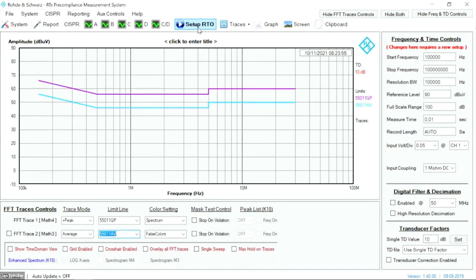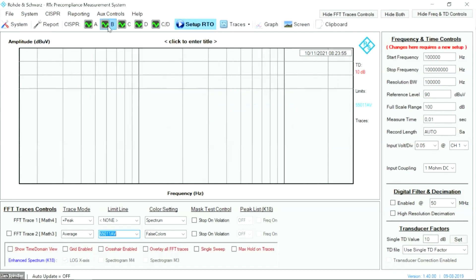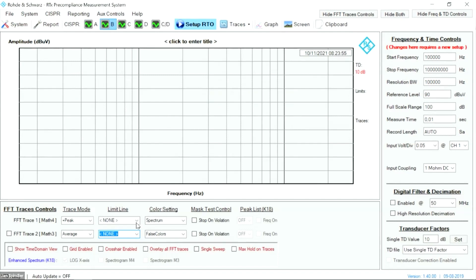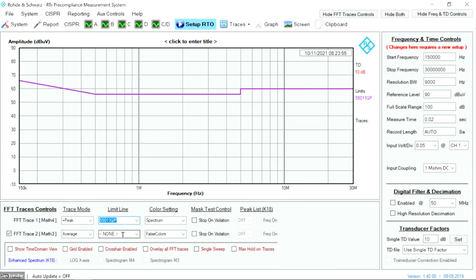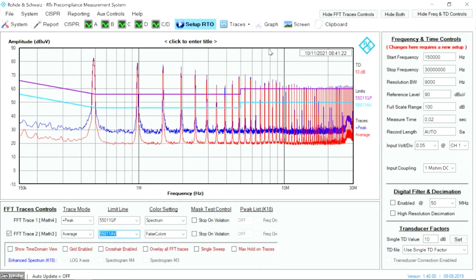I connect channel one to the output of the line impedance stabilization network. Let me set the frequency range for option B — from 150 kHz to 30 MHz. One of the most important things to do in your company is to replicate the results you have in the official laboratory. This is not easy. You need to prepare a setup with metallic plates, and you need to take care about the noise in your lab's mains network — a lot of things that make this test less easy than it looks at first impression.